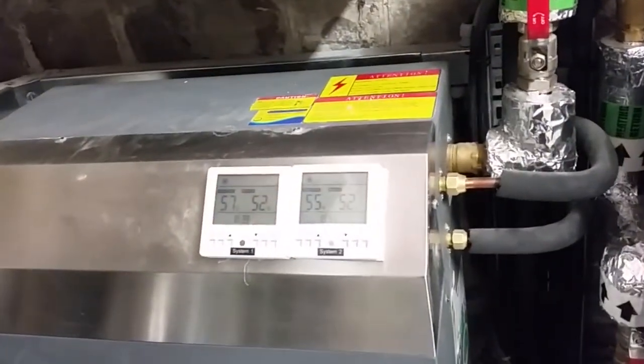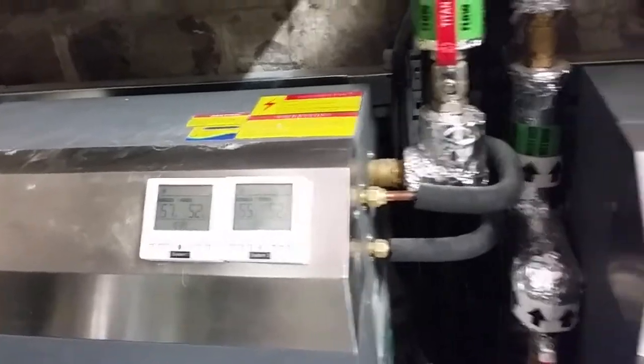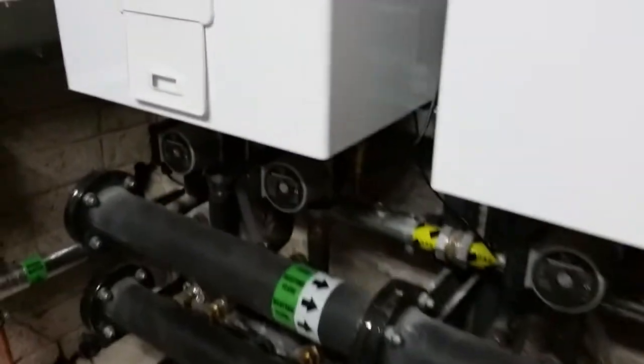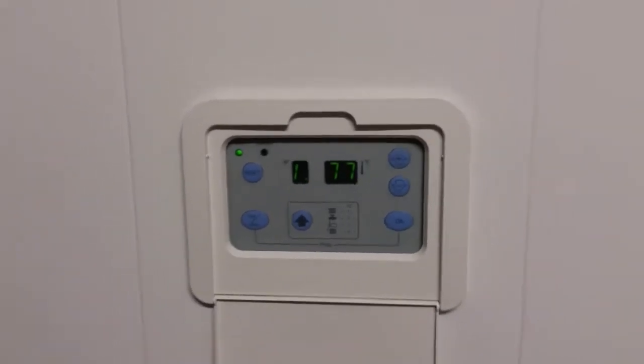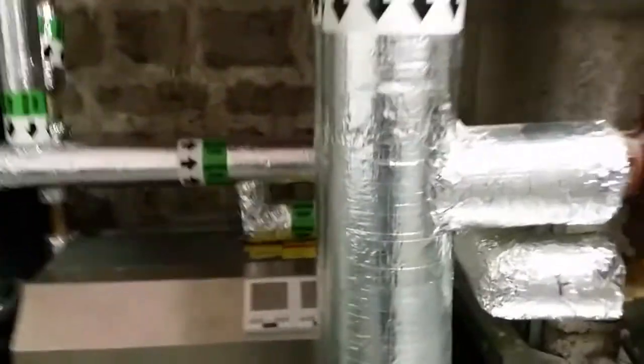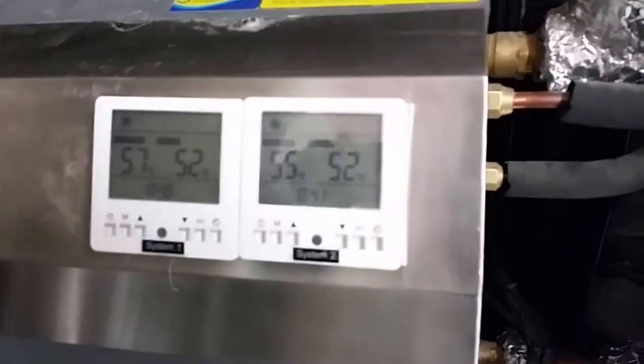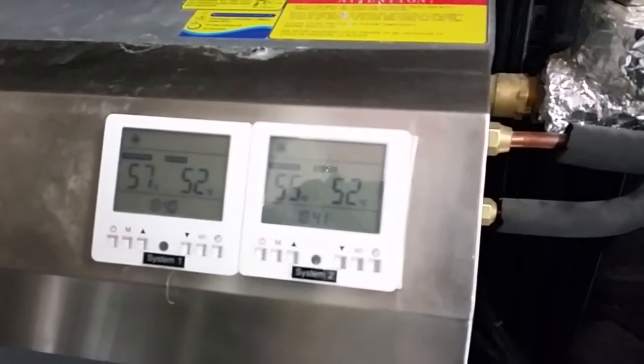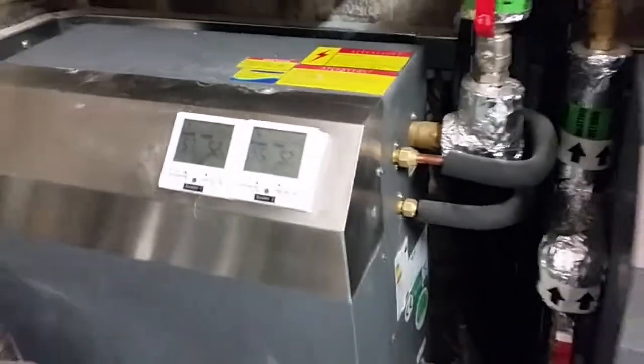The reason the gas boilers are calling alone is that there is a hot water call, and in a hot water call situation, the heat pumps cut out and let the gas boilers continue to bring it to full temperature. So the gas boilers are bringing the temperature up, but the heat pumps are switched off because they've reached 55 degrees. If the return water drops, then it can come back in again. The heat pumps will be back in. The heat pump and gas boilers would work together at the start of the hot water cycle, but as the water temperature rises in the return, the heat pumps will then switch off. You can see the gas boilers at 77 degrees.